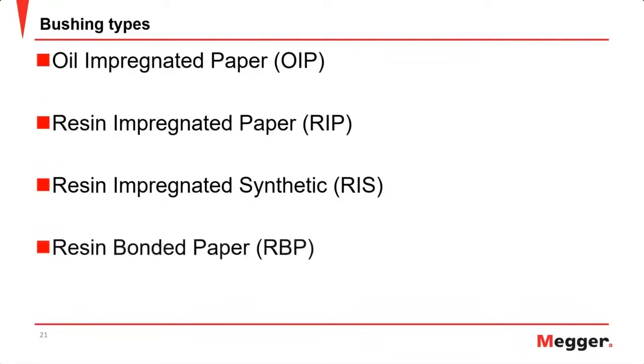The next technology, and this is mainly used on lower voltage bushings, would be resin bonded paper. This is where the sheet of paper itself has the resin to fill in the voids before it is wrapped around the foil of the bushing. And then finally, we just have cast epoxy bushings, where it's just a very simple process of creating a bushing where you don't need that capacitive grade for the application.